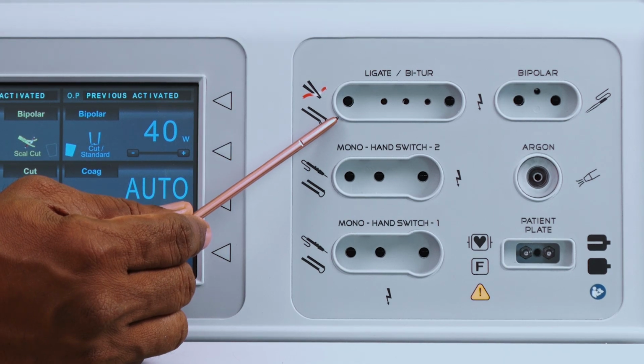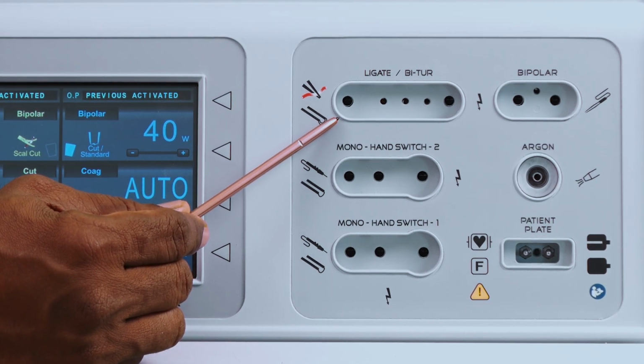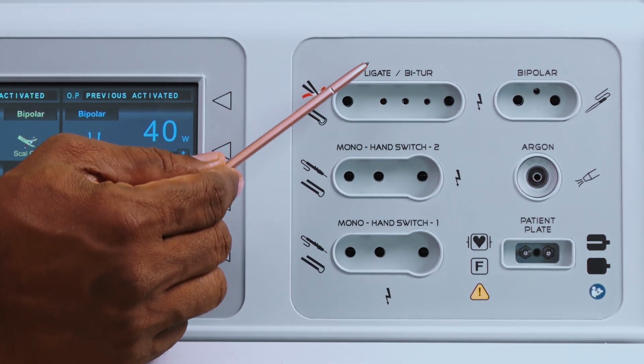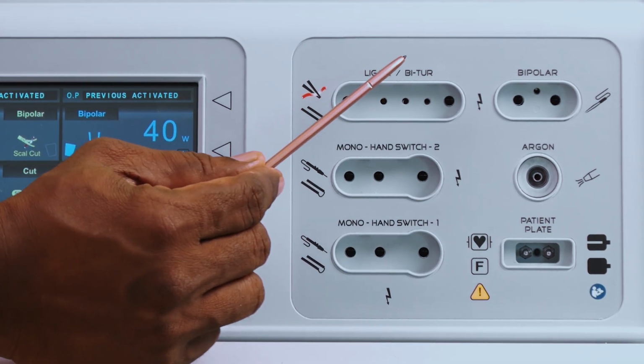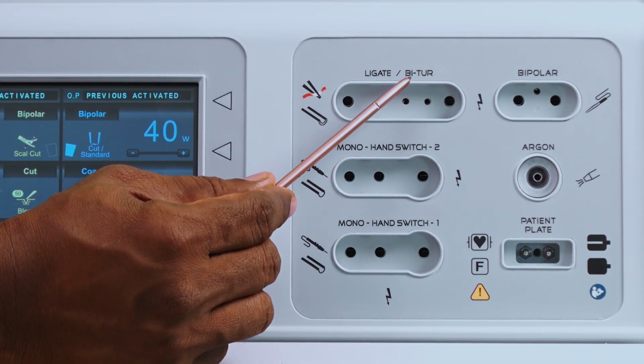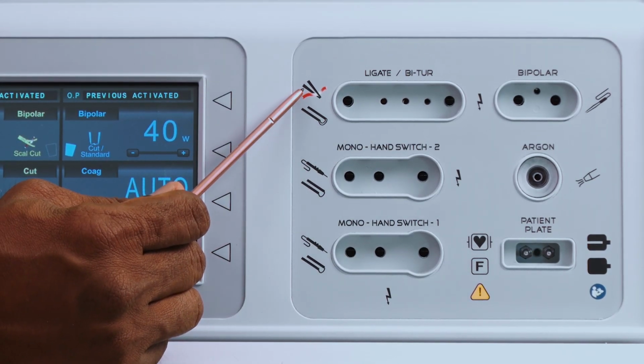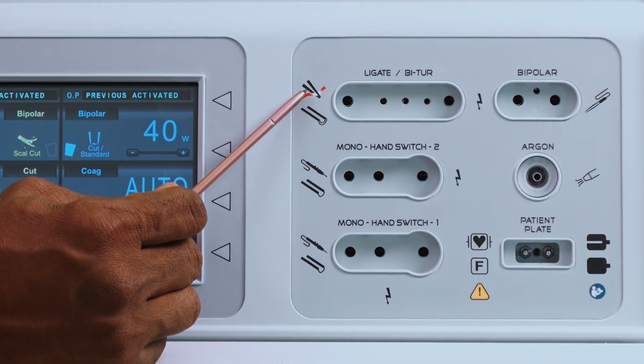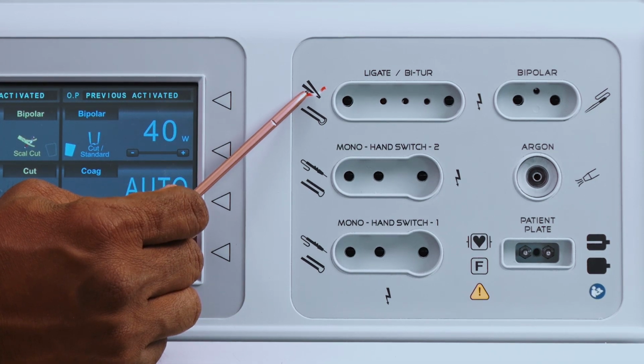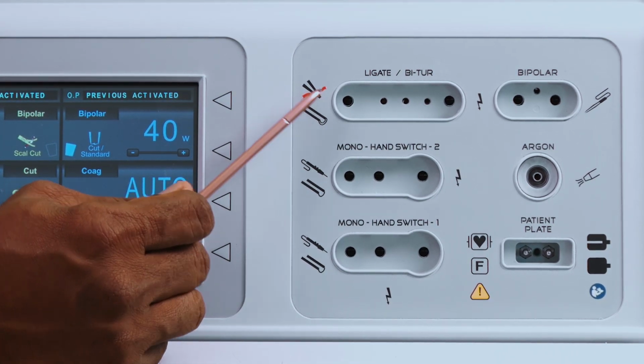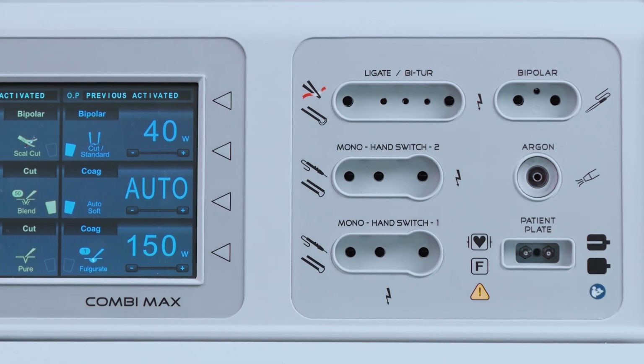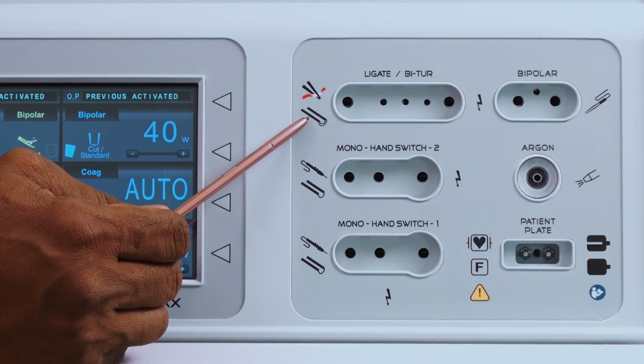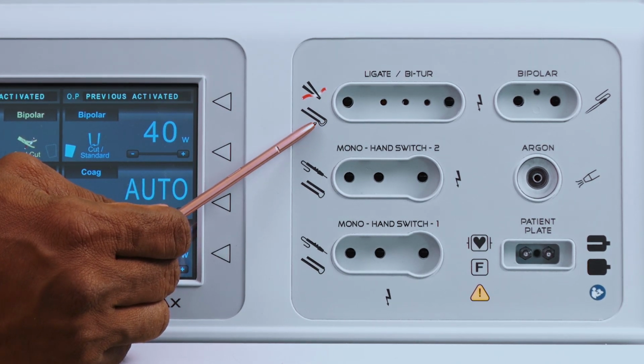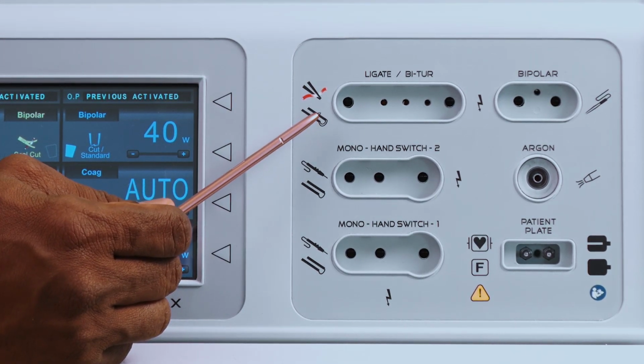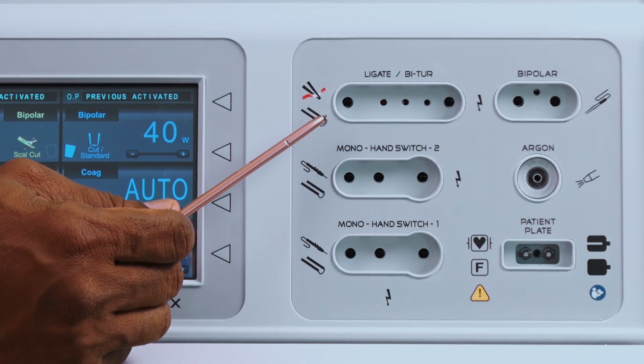This port is multifaceted, which means it can be used for two different surgical applications: vessel sealing, that is ligate, or BITUR, which is bipolar saline resection. When you choose ligate, it can be used for vessel sealing and it can seal the vessels up to 7 mm in diameter. It supports both 5 mm and 10 mm vessel sealing instruments. When you choose BITUR, it allows you to perform surgeries based on bipolar saline resection like TURP, TCRE, etc.